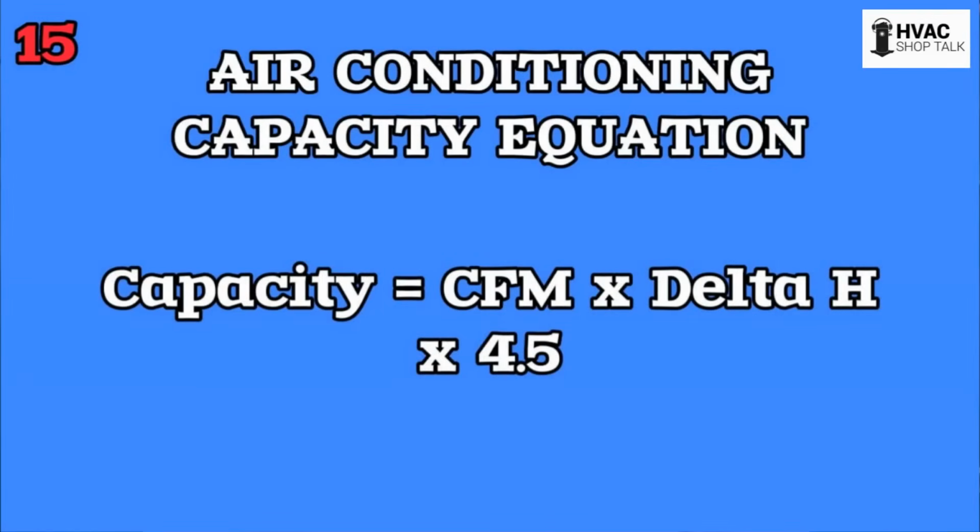Where you might have a 15-degree split, maybe you get 17 or 18. Another good reason to have Measure Quick: it'll tell you when you're outside the parameters and your airflow is too low because your split's too high. Enthalpy split is similar. It's not as large a number, but it'll get larger as the CFM goes down, to a certain extent. So you'll notice the same thing between the two of them.